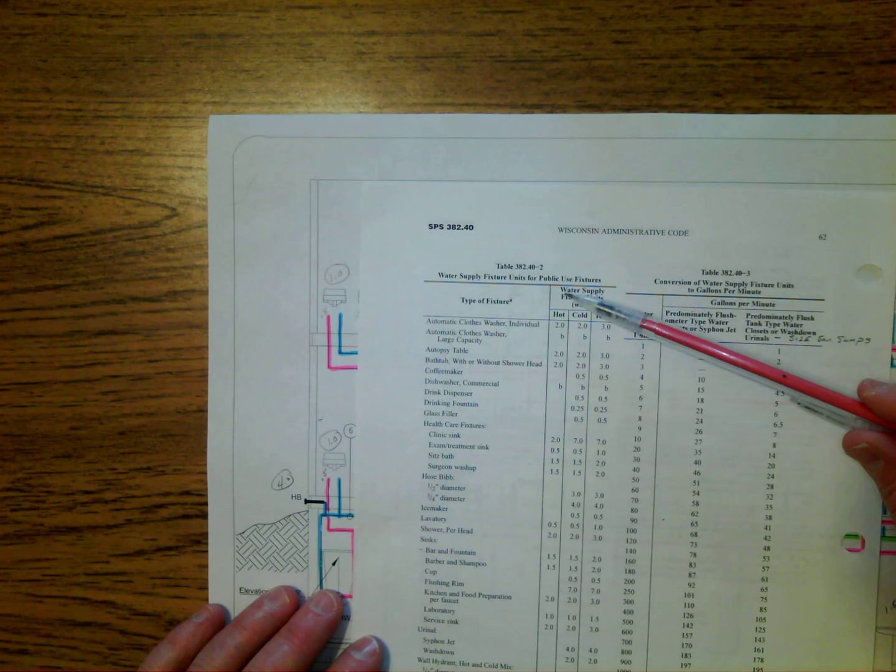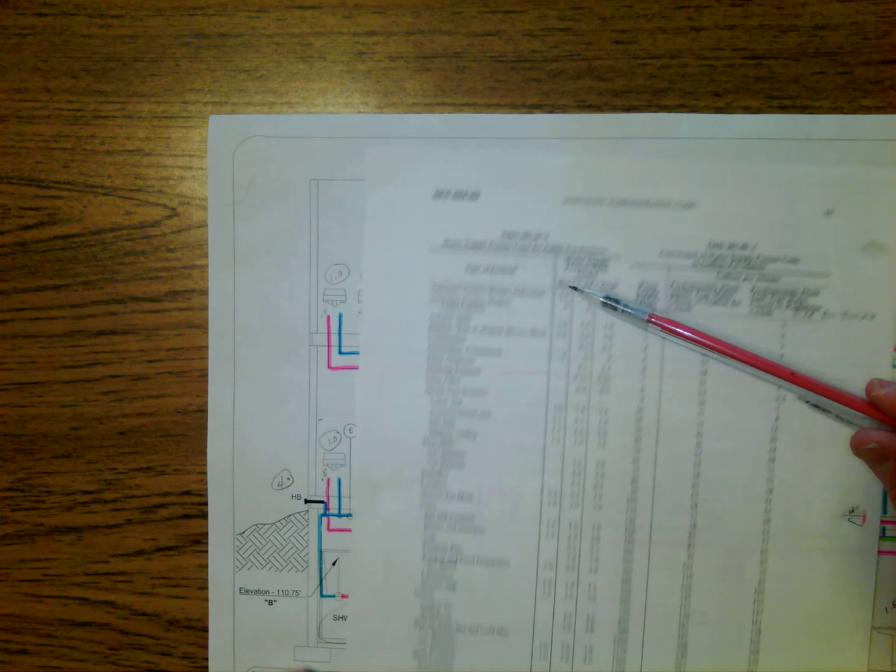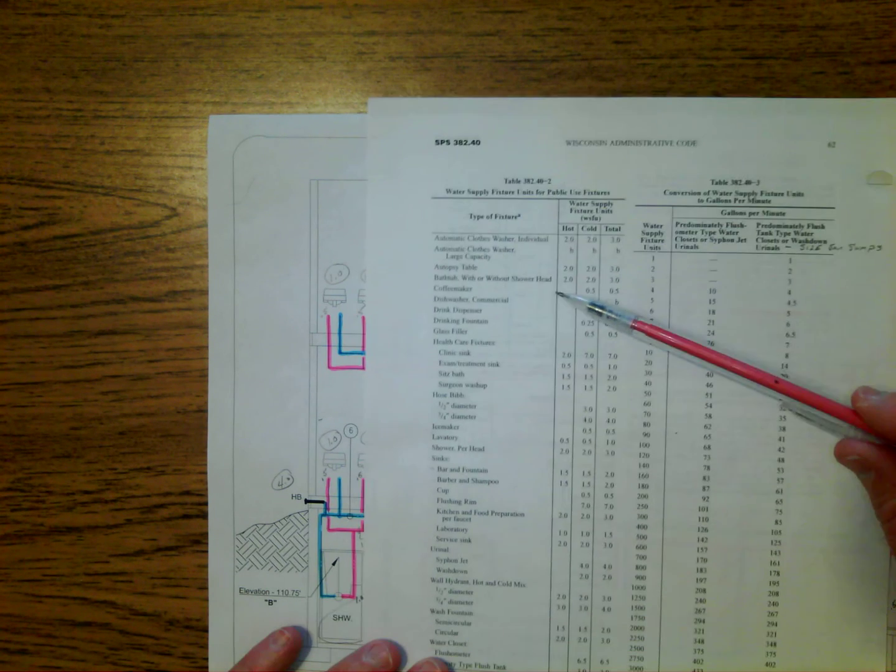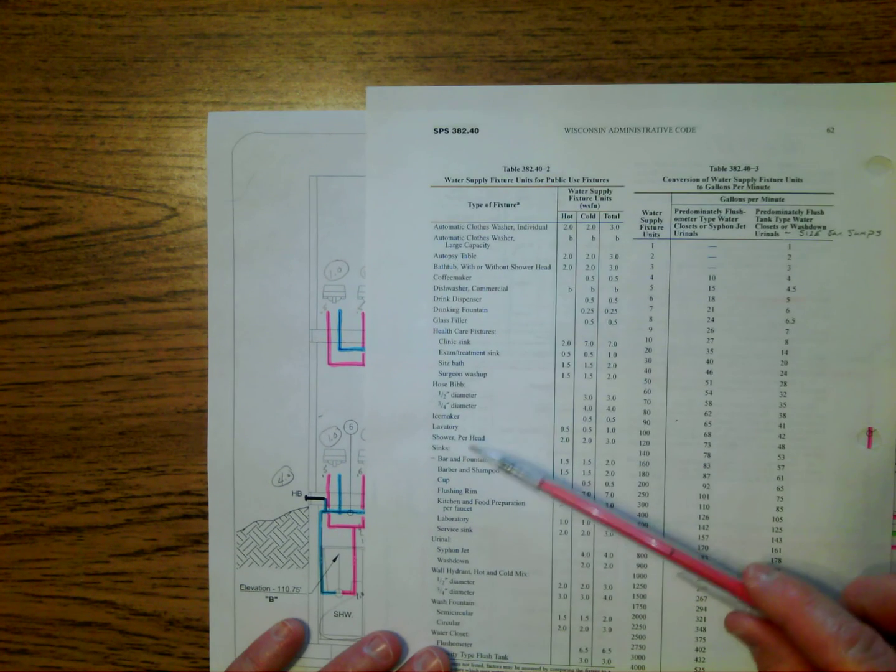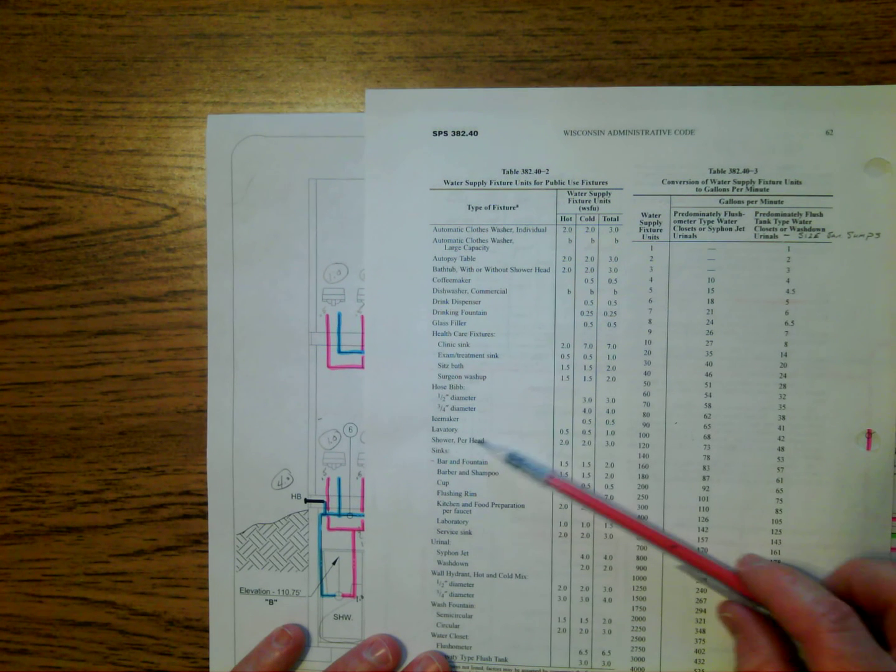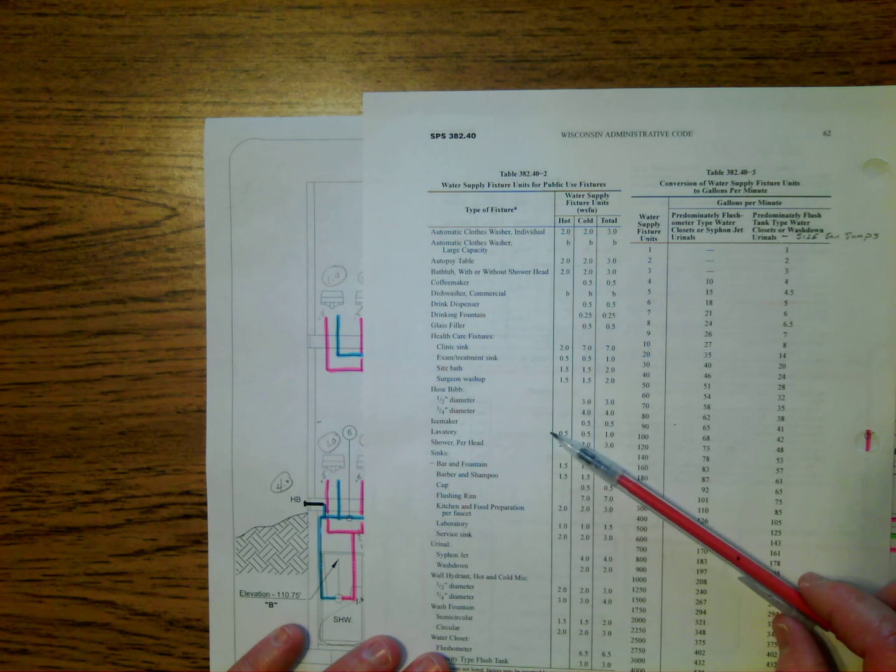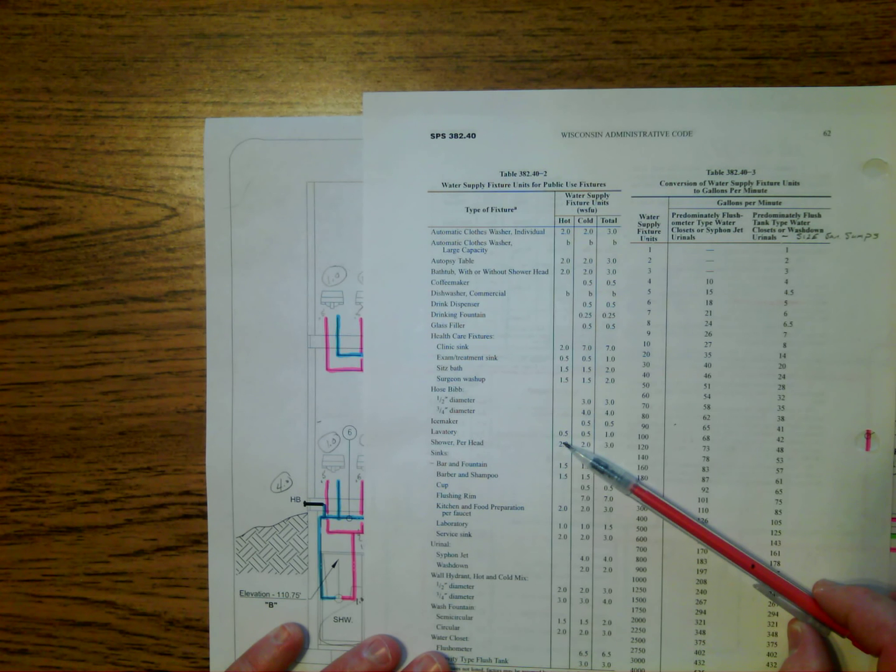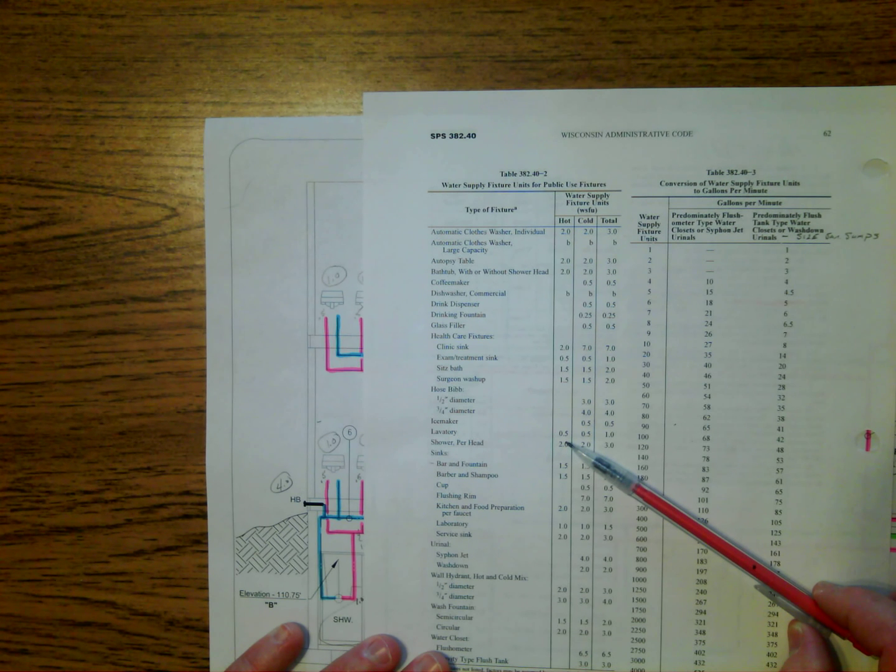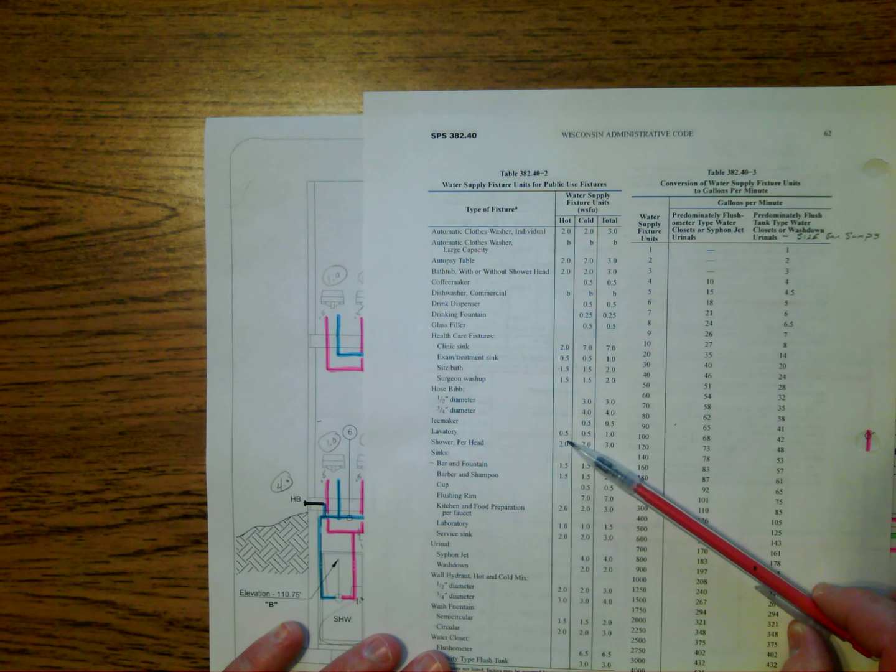Of course, this is a public building, so I went in and I found lavatory sinks, went over until I got to the hot column, and found out that each hot water line serving a lavatory sink had a load of 0.5 on it.